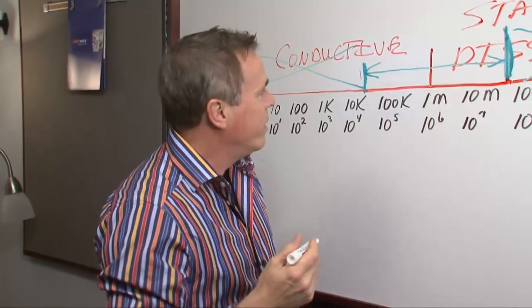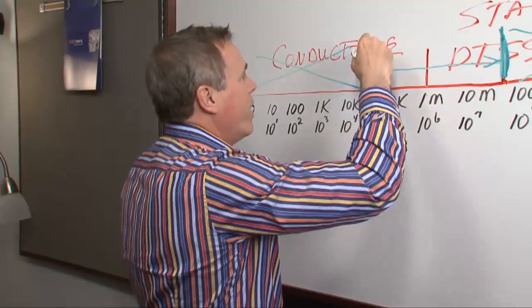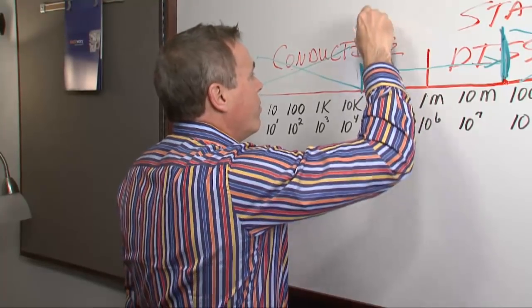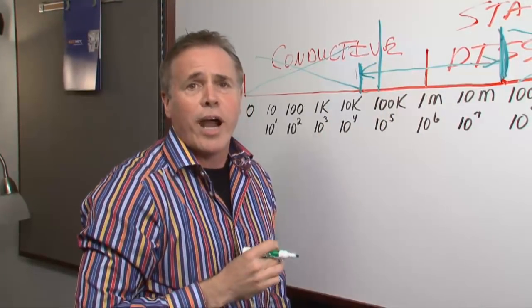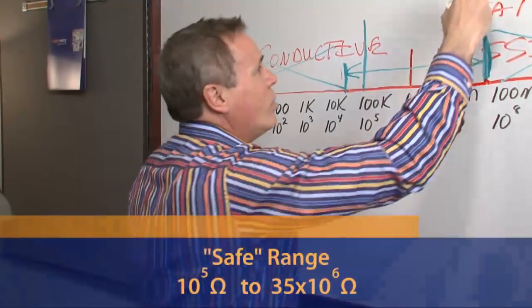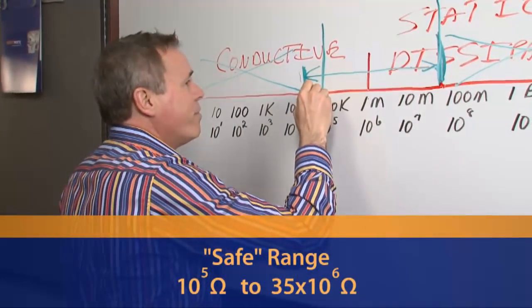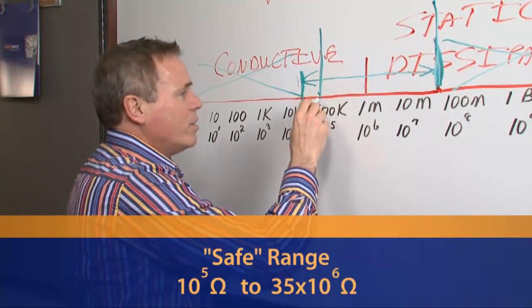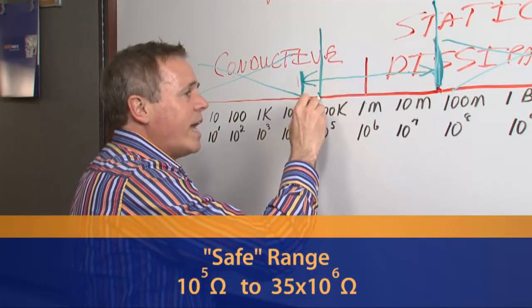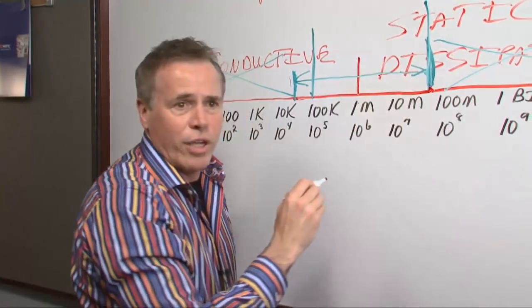So what we look at is a little bit of margin of error. We like to use 100,000 ohms as our minimum resistance. So when we talk about a floor that's going to be safe but still work, what we're talking about is a floor that will measure between 100,000 ohms and 35 million ohms.